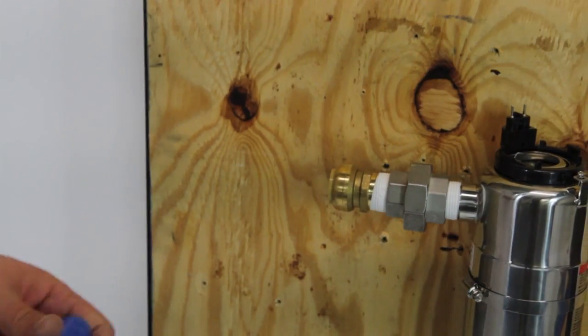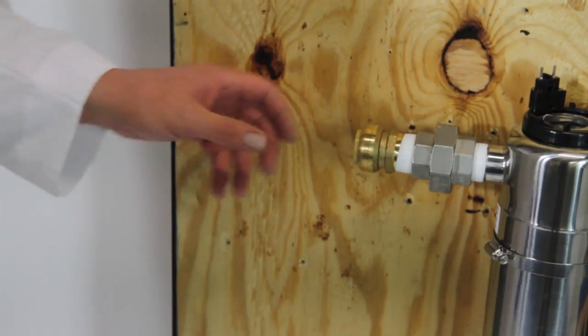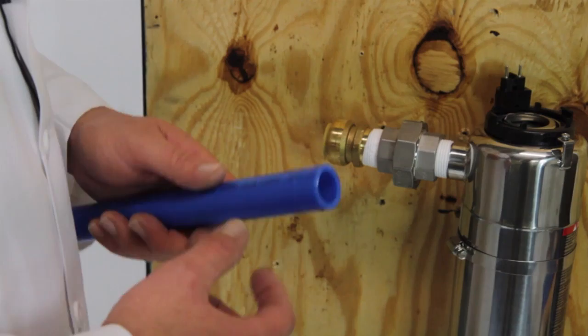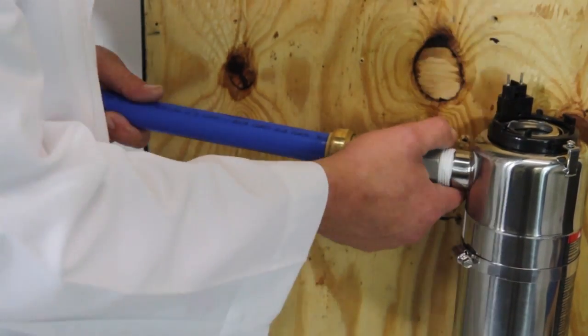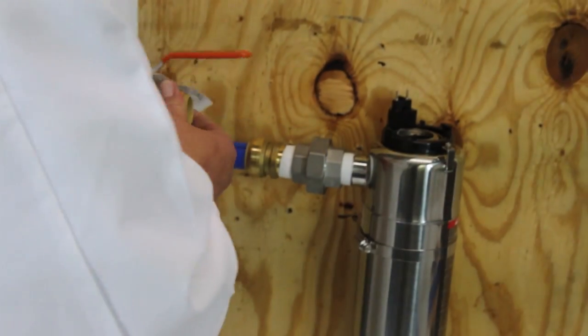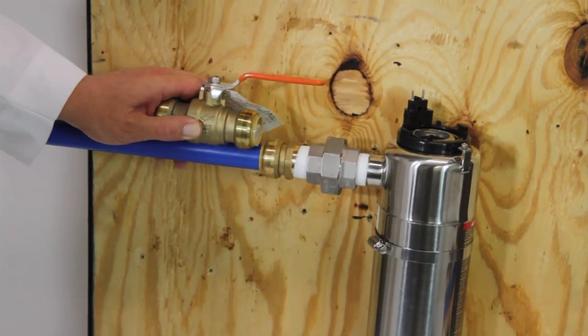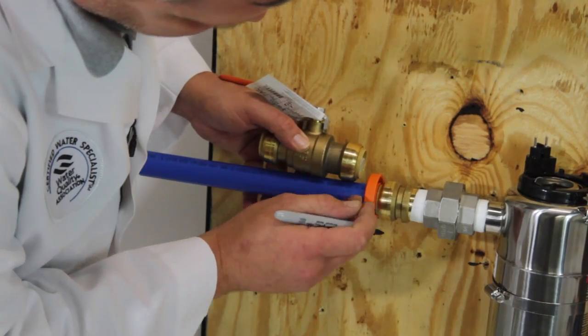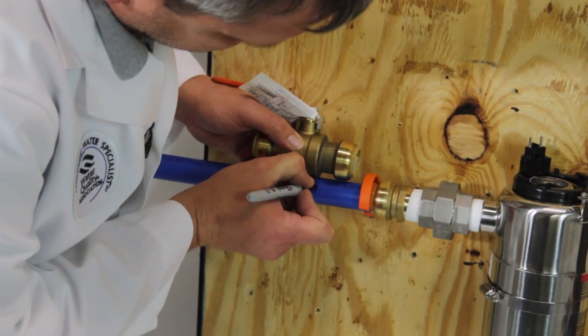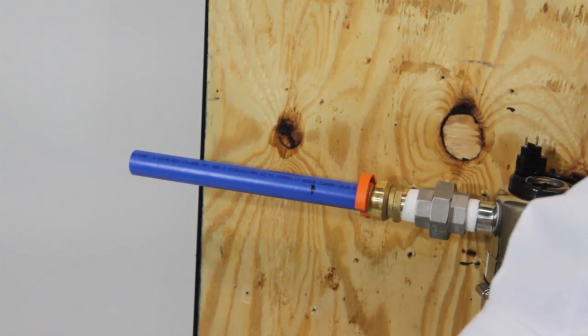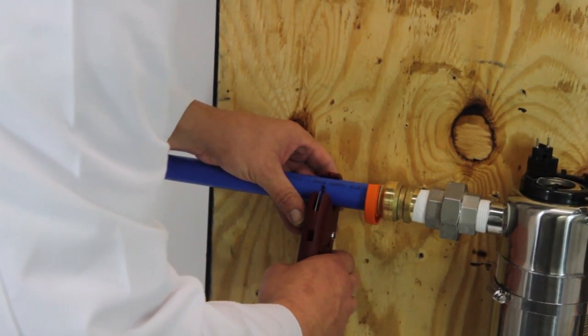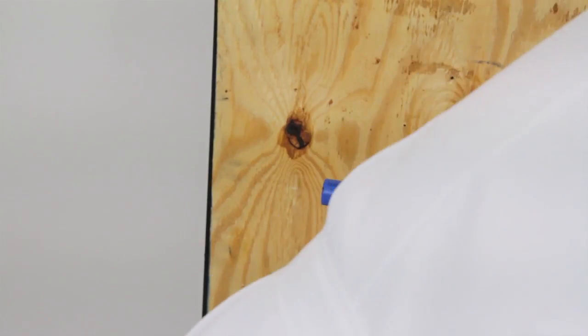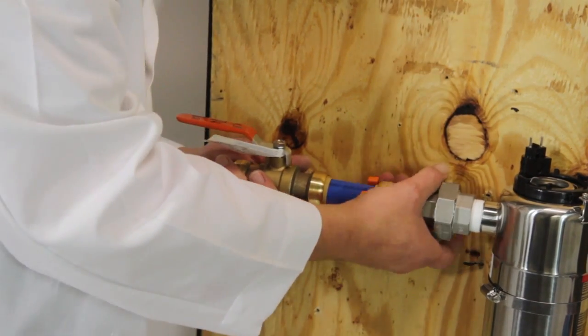We're going to start plumbing now, so the first thing I'm going to do is get my pipes over with a T and we're going to put our valves in. What we need to do first is cut a short nipple so we can put our shutoff valves in. The shutoff valves will also be quick connect on both sides. I'll push this all the way in where it goes and we're going to line up our shutoff valve. With these SharkBite fittings, the fitting itself is going to come back all the way to this shoulder. Use that as your measuring point, use our tool, put it right on the mark, cut your pipe off. Now we can slide our SharkBite valve in place.